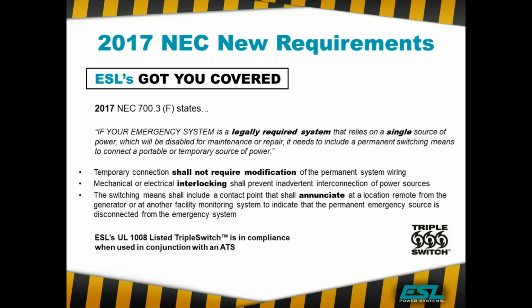A lot of states now, assisted living facilities are legally required to have a source of permanent backup power. So data centers, police stations, fire stations, there are a lot of legally required systems out there that you'll have to know about as you're designing things, and they need to be backed up. Sometimes, again, depending on the code, it may not be the whole facility that has to be backed up, just life safety or critical infrastructure systems, but they do need to have backup power.